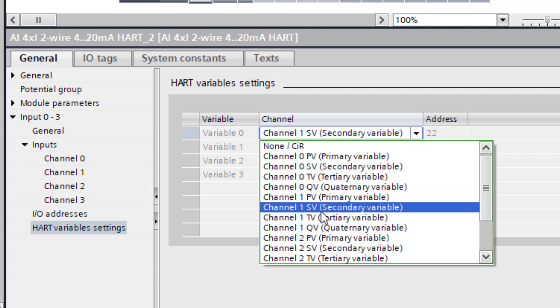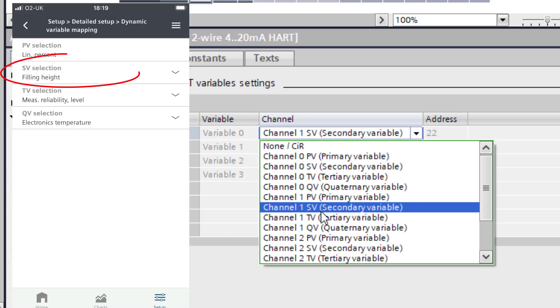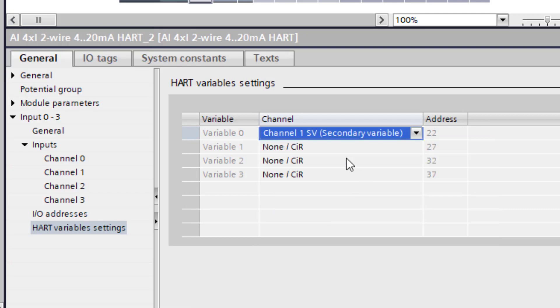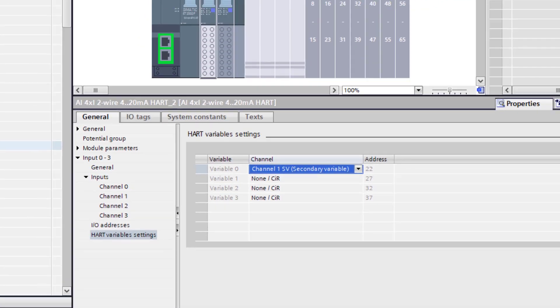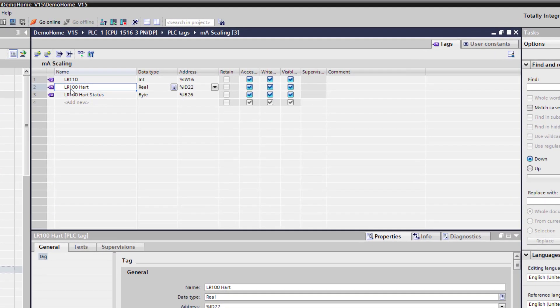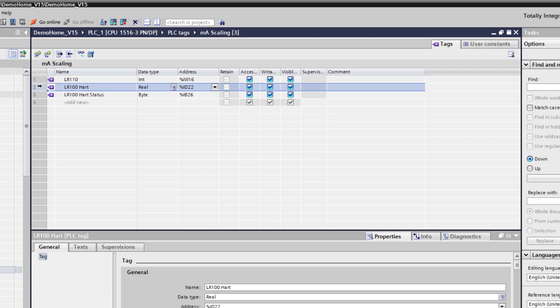And this particular device I want to read the raw level value. I don't want to read a percentage because I'd have to scale it again within the PLC. So I'm going to program that on the device to output that as the filling level. So that's already set. What you would have to do then is to compile the hardware and download it because you've made a hardware change. And I have then added those values into my tag table. So in here you can see the double word. And what I'm going to do is I'm going to copy those into a watch table.